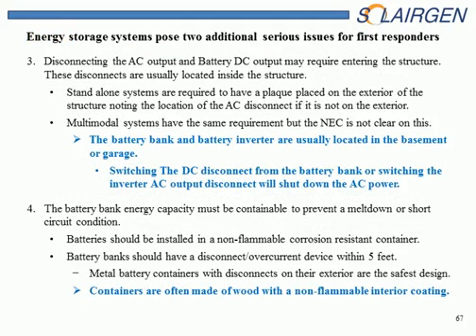PV systems with energy storage pose two additional serious issues. Where is the AC and DC disconnect? On standalone systems, they will have a plaque more than likely, and the AC disconnect will be on the outside of the structure. Not guaranteed to be out there, but more than likely it will have a plaque identifying the fact that there is a standalone system in place. Multimodal systems have the same requirement, but they may not have the plaque outside, so that's something to be cautious about.